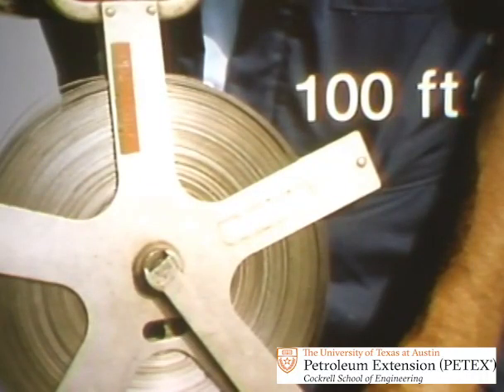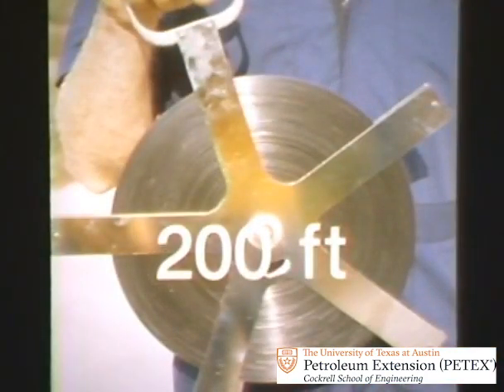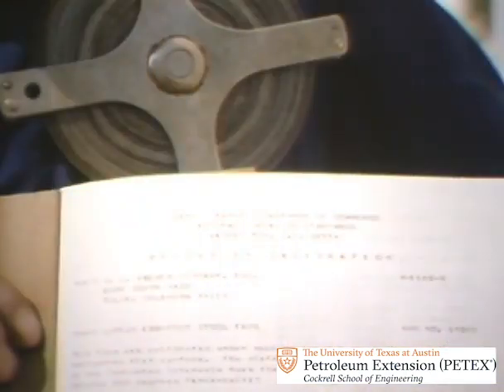This standard tape's 100 feet long, but other lengths are available. Generally, the working tape has to be long enough to go all the way around the tank's circumference. In this case, 200 feet does it. Regardless of length, the standard tape is called standard because it's calibrated by the National Bureau of Standards.